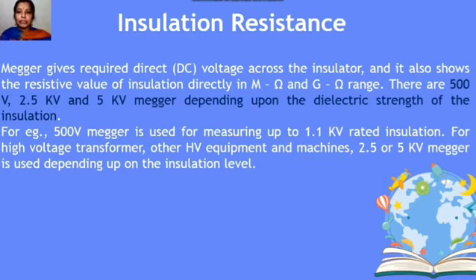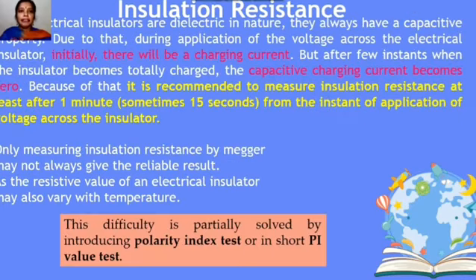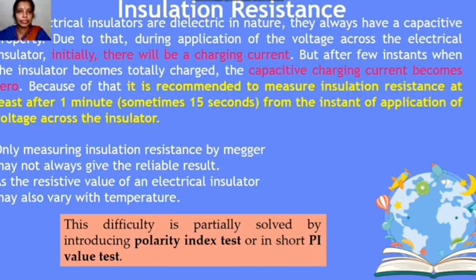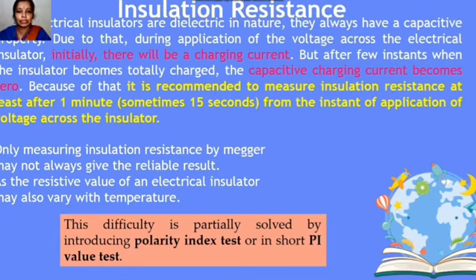All electric insulators are dielectric in nature and have capacitive properties. During application of voltage, initially there will be a charging current, which will decay exponentially to zero after a few seconds. It is therefore recommended to measure insulation resistance at least after one minute from the instant of application of voltage. Measuring by megger alone may not always give reliable results as insulation resistance also varies with temperature. This difficulty is partially solved by the polarization index (PI) test.